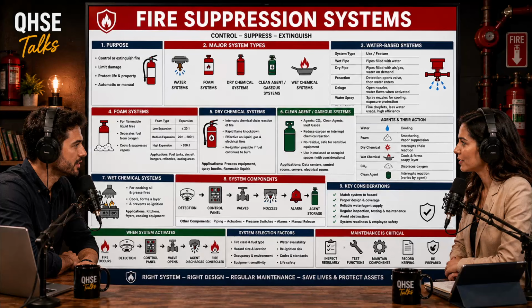But there is a massive inherent life safety contradiction here, right? If the goal of safety is to protect human life, dumping a room full of CO2 seems counterproductive. It is a very severe life safety hazard. CO2 is an asphyxiant gas. By design, a total flooding CO2 system is engineered to reduce the ambient oxygen concentration from the normal 20.9% down to below 15% to kill the fire. Where human beings need about 19.5% oxygen to maintain normal cognitive function.